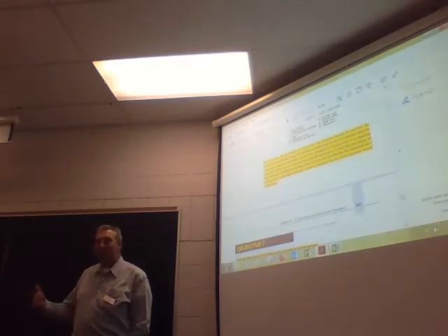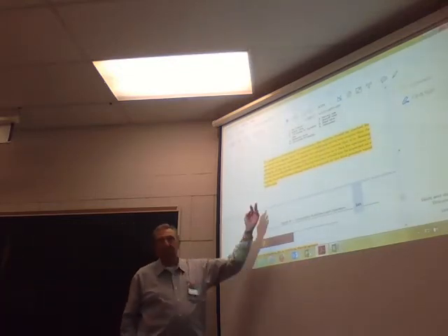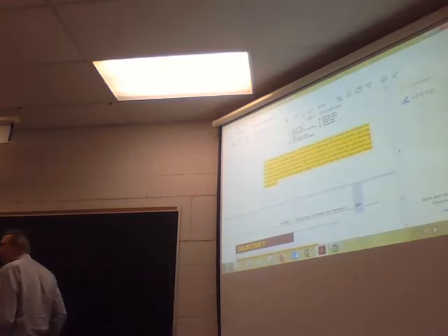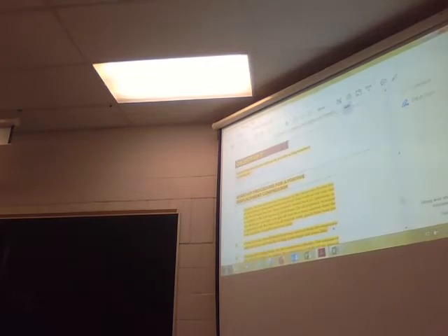Your air dryer is broken, or your bypass is open, because your dry receiver should have dry air in it, right? The air receiver should also be inspected on a regular basis and hydrostatically tested as required by local pressure vessel authorities. There's actually a code out there that will tell you about pressure vessels and when they are to be checked.